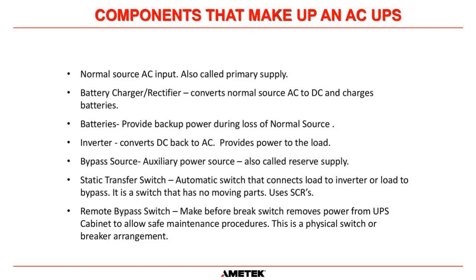Then we have an inverter, which converts the DC back to AC and provides power to the load circuits. We also have a bypass power source — also called the reserve supply or auxiliary supply. There's also a static transfer switch, which is an automatic switch that connects the load to the inverter or to bypass using SCRs — it has no moving parts, which is why it's called a static switch. Finally, we have a remote bypass or manual bypass switch, which is a make-before-break switch with physical moving parts that removes power from the UPS cabinet for safe maintenance.